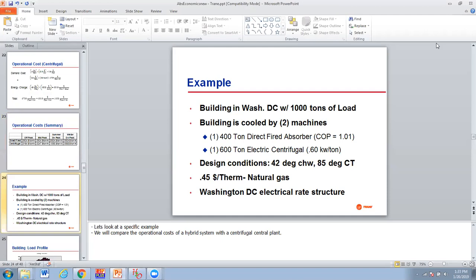We have a 400-ton direct fired absorber where the COP is listed at 1.01, and the other is a 600-ton electric centrifugal at 0.6 kW per ton, and I think we calculated that last time. I think it was 5.86 was the COP on that one. Design conditions are 42-degree water leaving the chiller and 85-degree condenser water, the cold temperature coming out of the cooling tower supplied to the chiller. Our natural gas cost is 45 cents a therm, and a therm is 100,000 BTUs, 10 therms to a million.